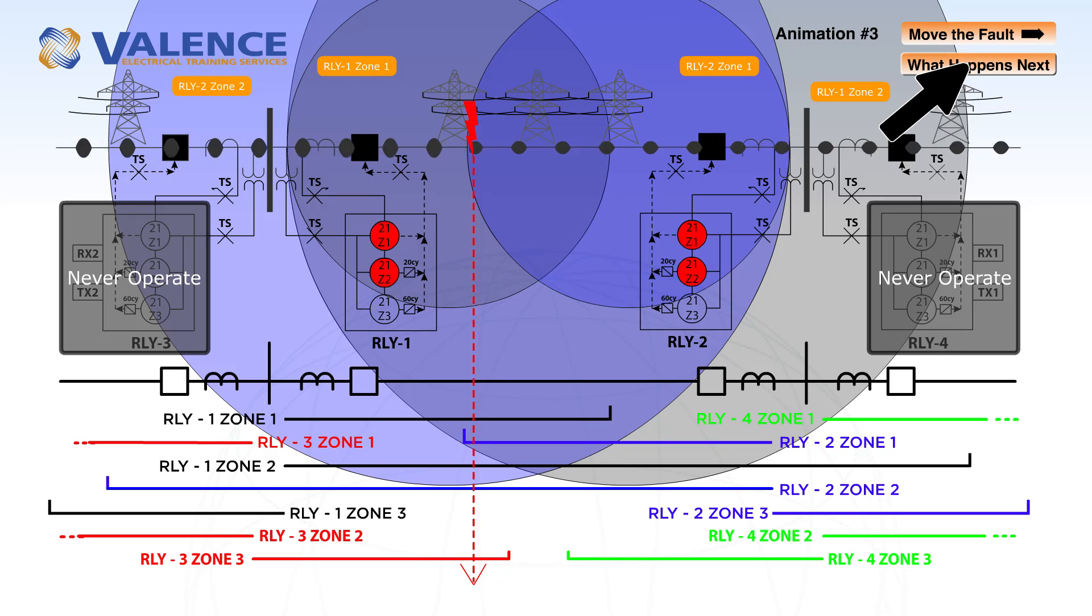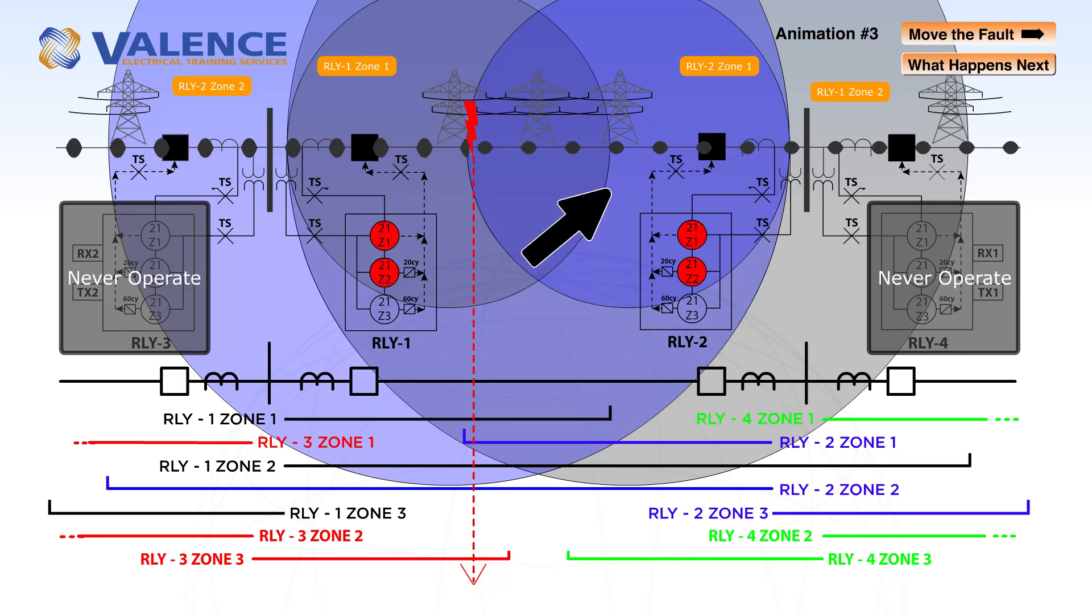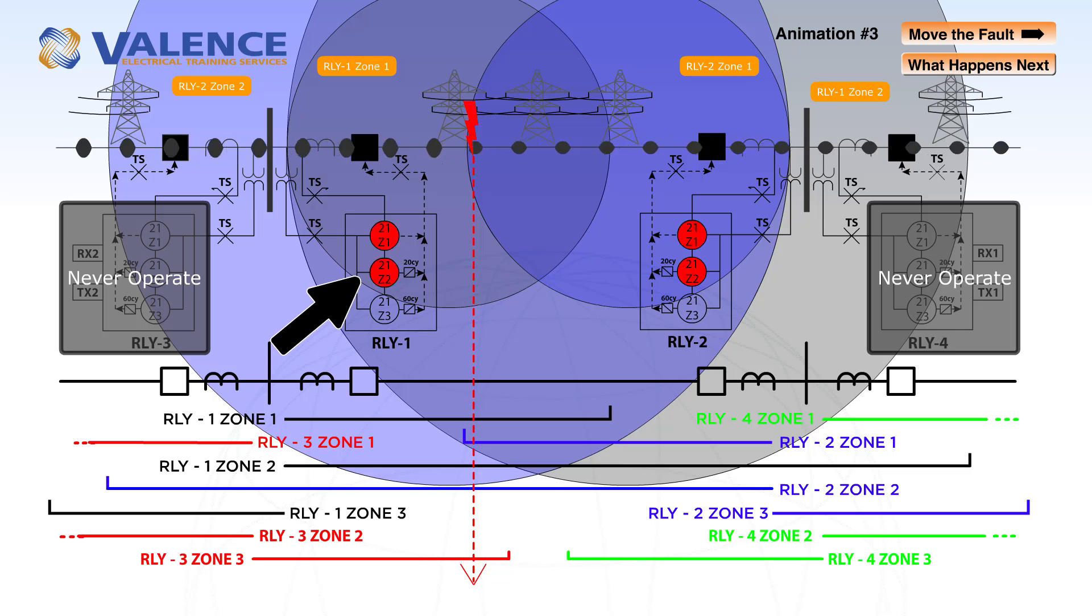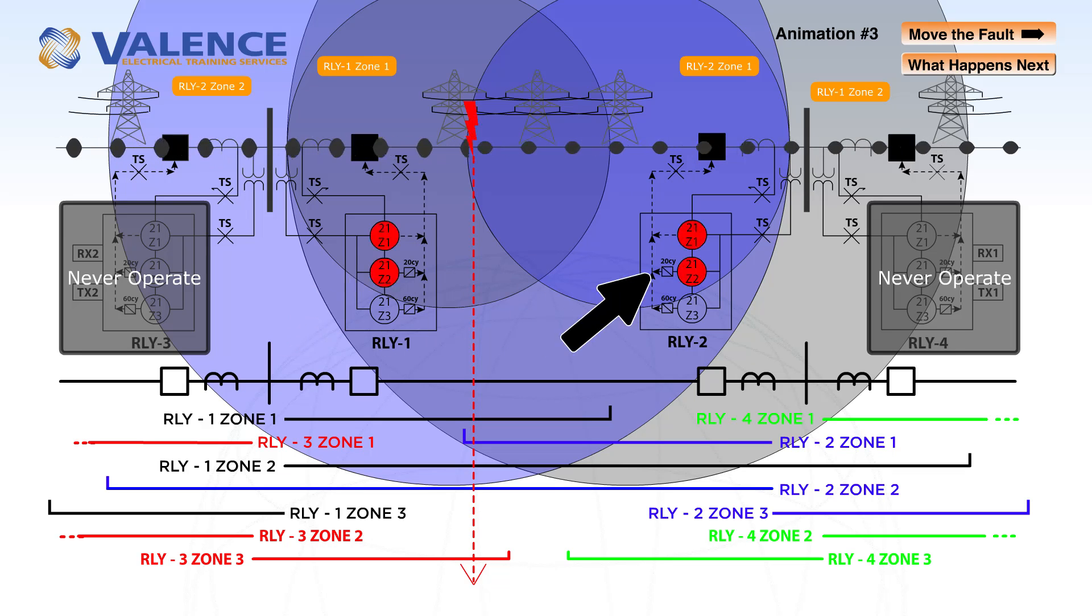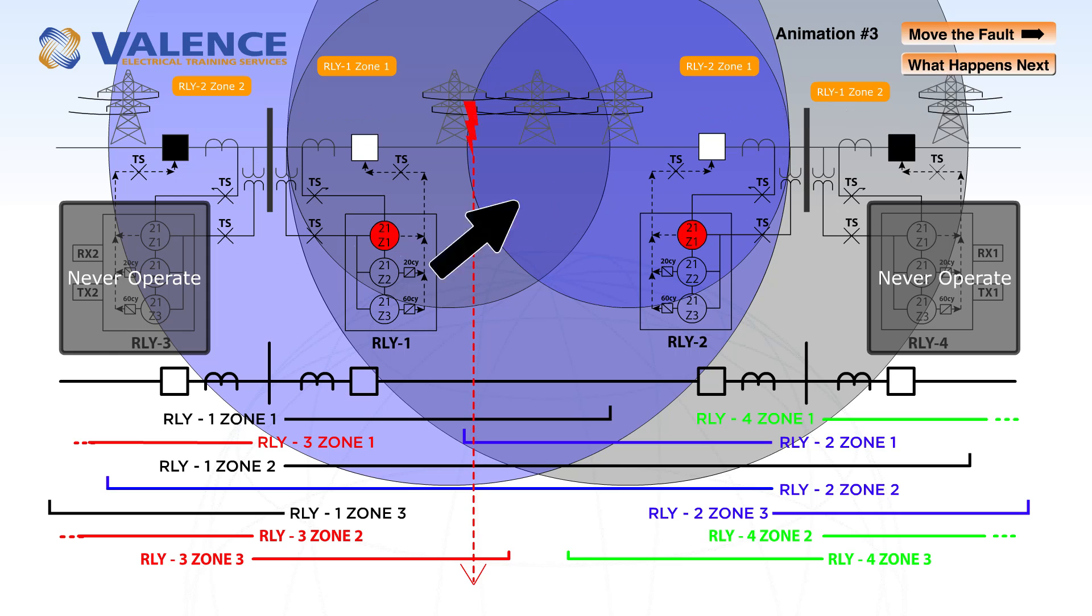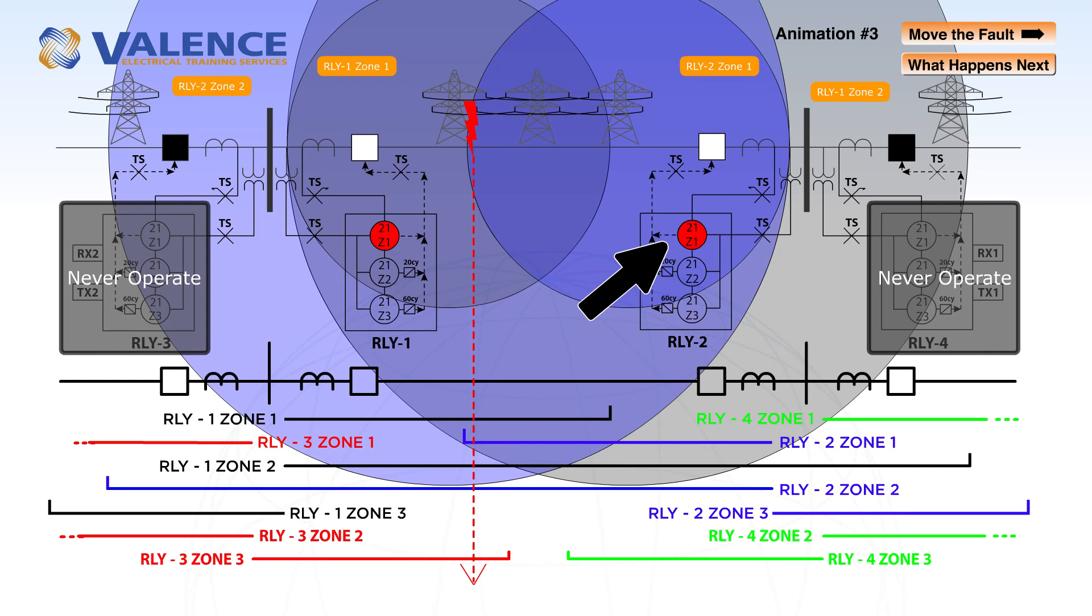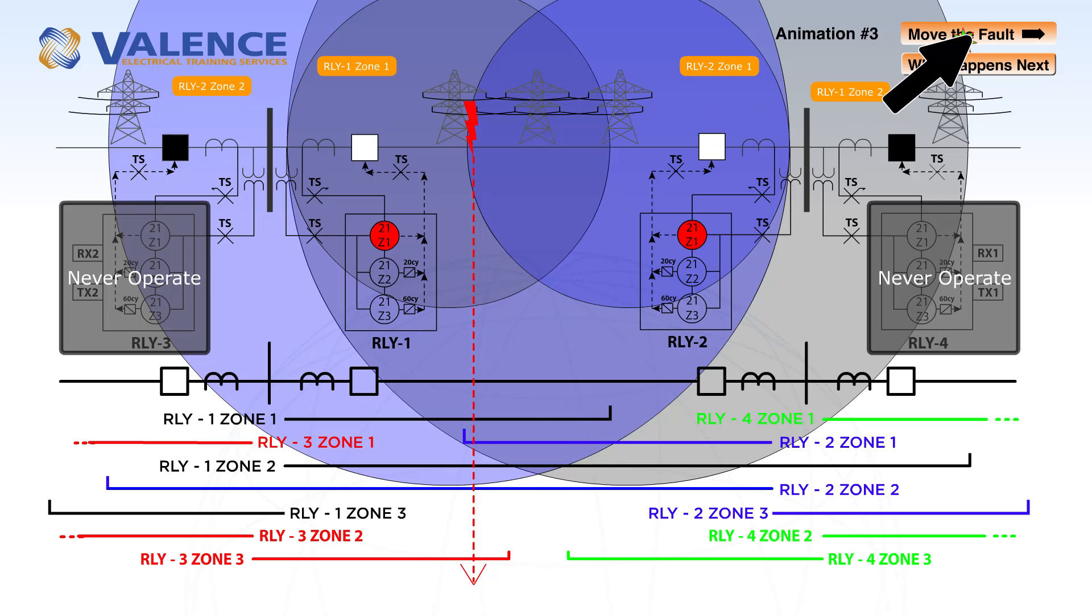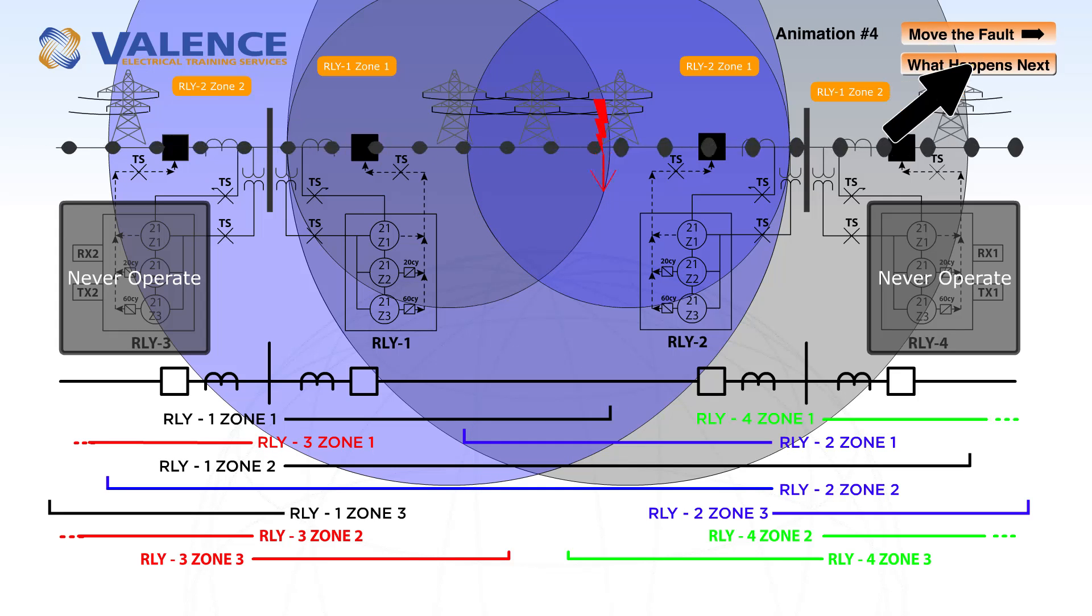When we click the what happens next button, we can see that zone 1 and zone 2 protection are both picked up in both relays. That means that both relays are going to operate instantaneously because we're in that overlapping region.